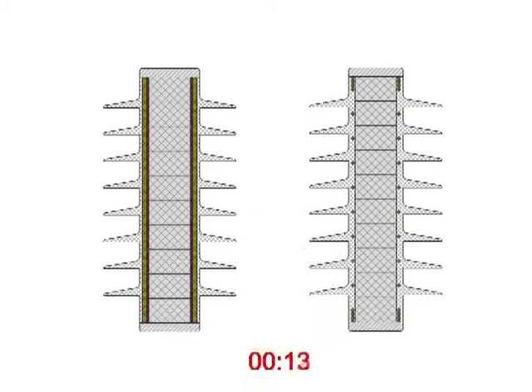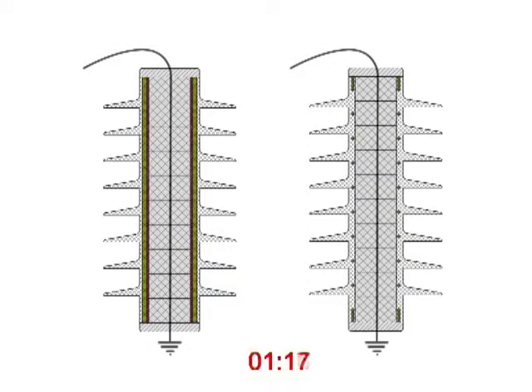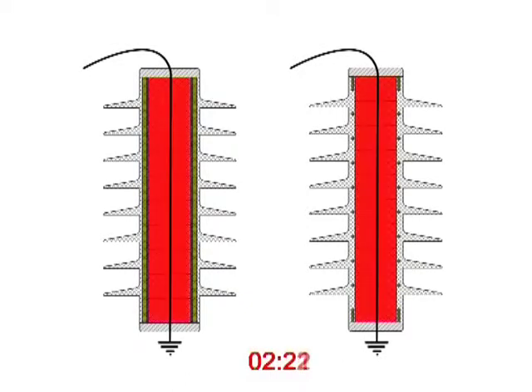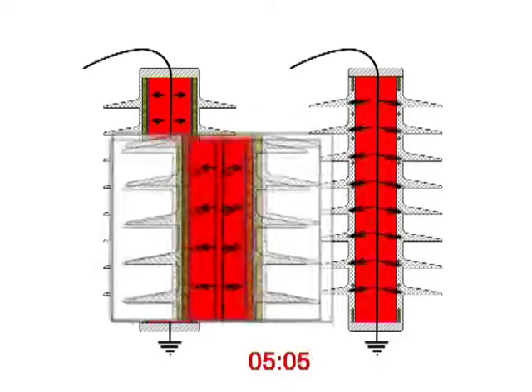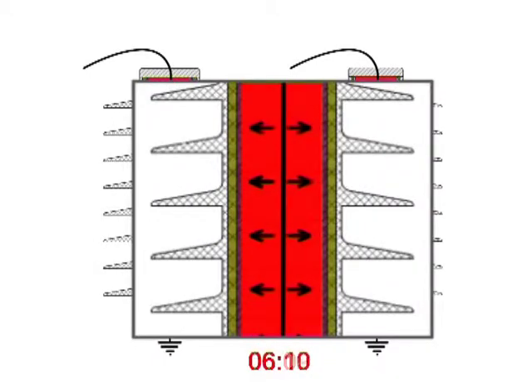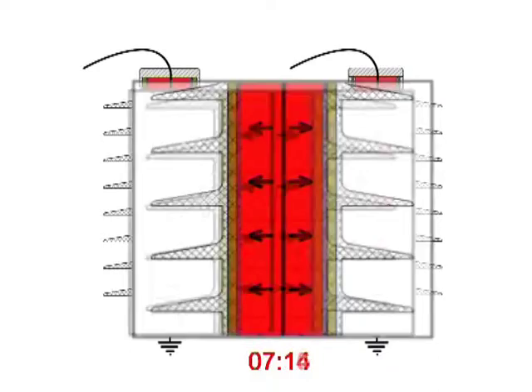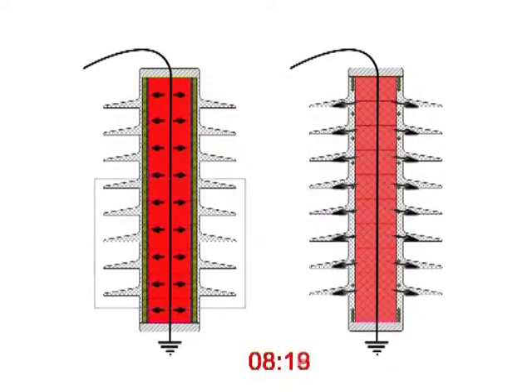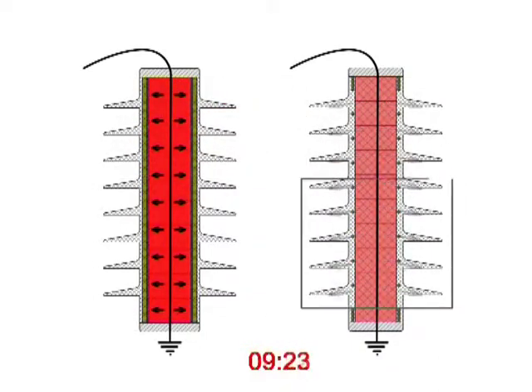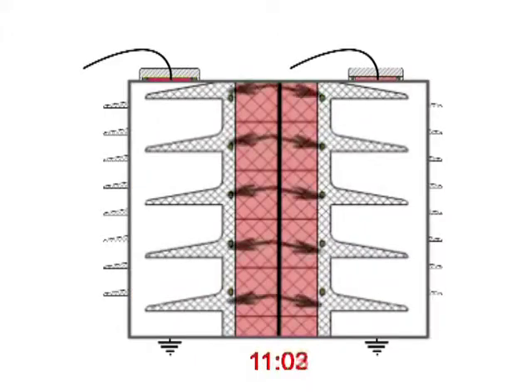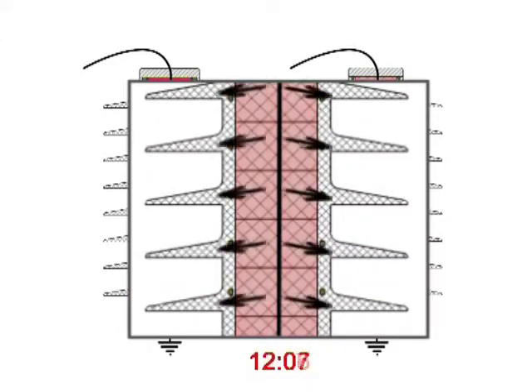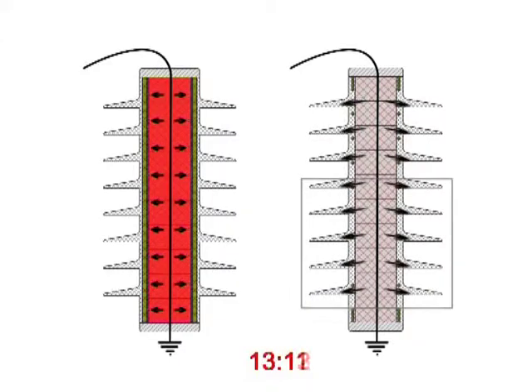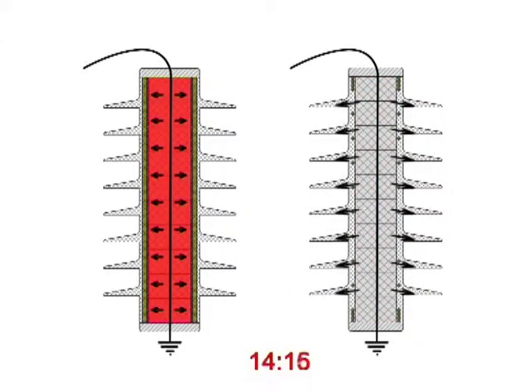The current flowing through the MOSA to earth can significantly heat the varistors due to limiting overvoltage. The functionality of surge arresters, to a large extent, depends on their ability to dissipate heat, i.e. cool down after exposure to a surge. Unlike the traditional design of surge arresters, there is no material with poor thermal conductivity between the varistors and the ambient environment, which ensures fast heat dissipation from the varistors.